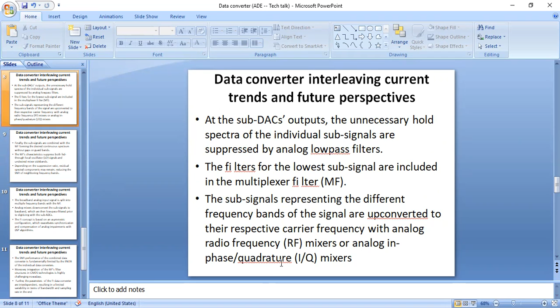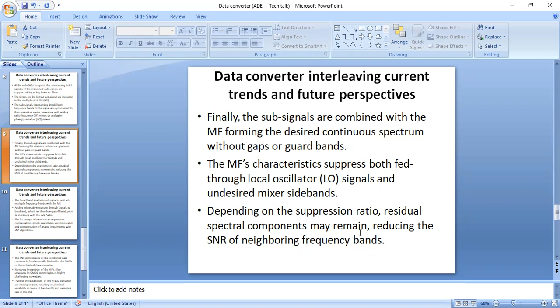The subsignals representing the different frequency bands of the signal are upconverted to their respective carrier frequency with analog radio frequency mixers and analog in-phase or quadrature IQ mixers. Finally, the subsignals are combined with the MF forming the desired continuous spectrum without gaps or guard bands. The MF characteristics suppress both fed-through local oscillator LO signals and undesired mixer sidebands. Depending on the suppression ratio, residual spectral components may remain, reducing the SNR of neighboring frequency bands.